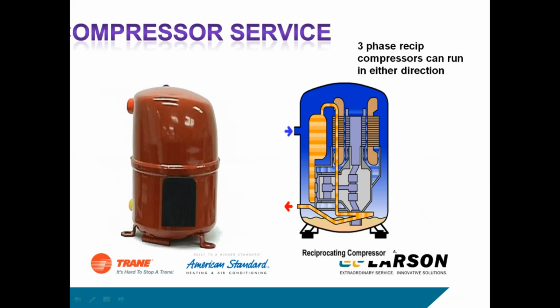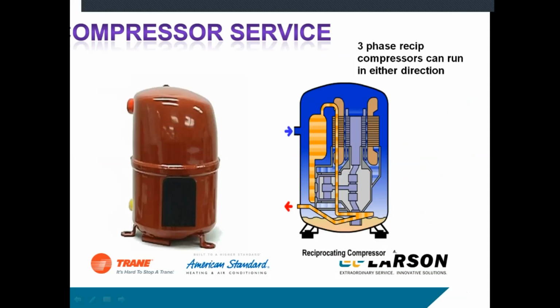I would say recips are probably not going to be around except for the really, really small stuff, reach-ins, that kind of stuff, and even that is turning into more scrolls and inverter-driven equipment. But when you looked at the old recip compressors, basically it was an electric motor, a crankshaft, and a piston, and a set of reeds here. The piston would pump up and down and draw the refrigerant in across the coil, across the motor, run it through the piston chamber, and pump it into a high pressure gas, in and out to the system.